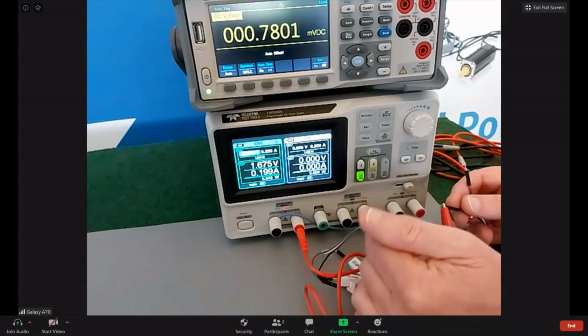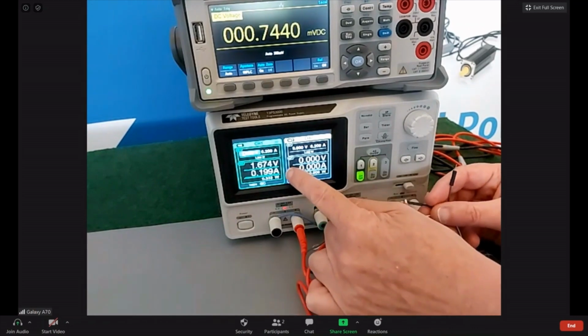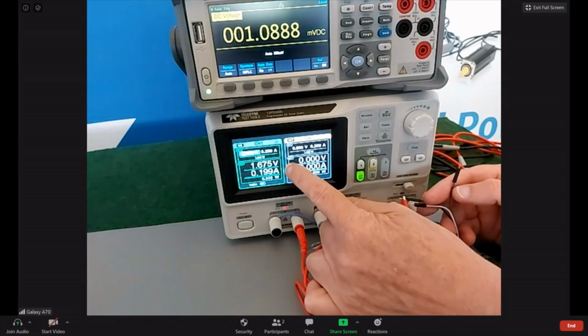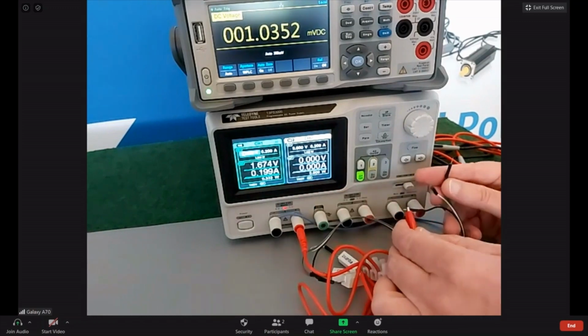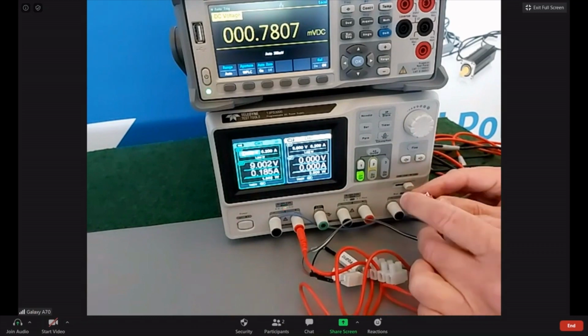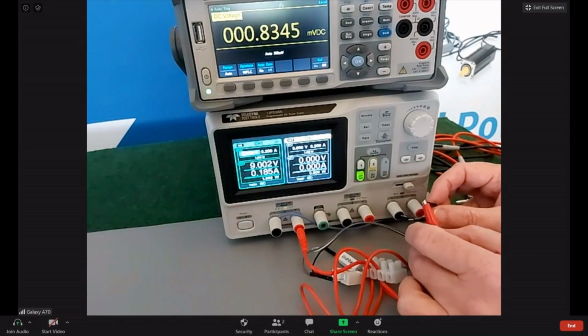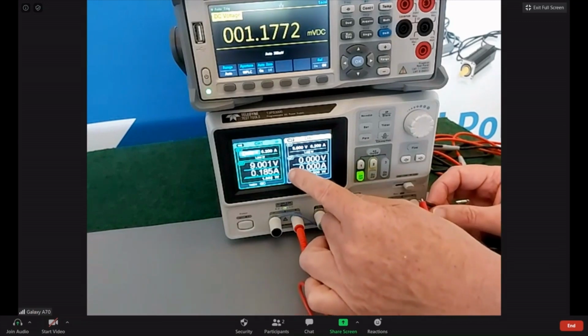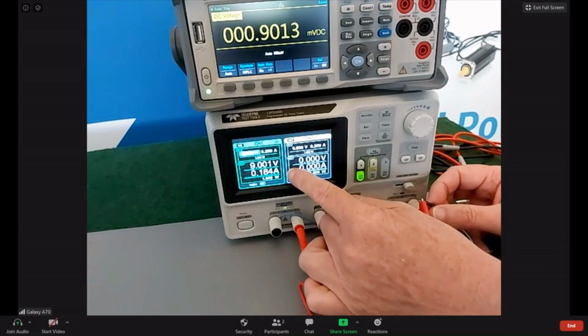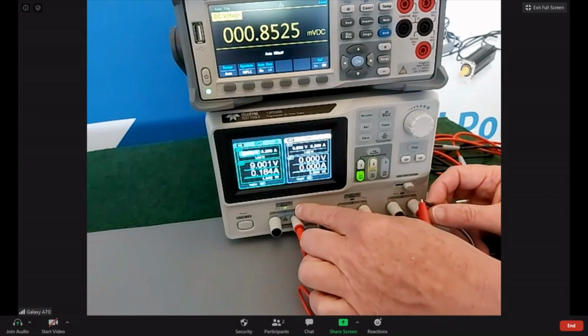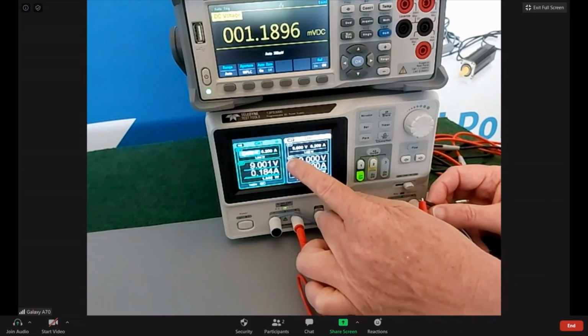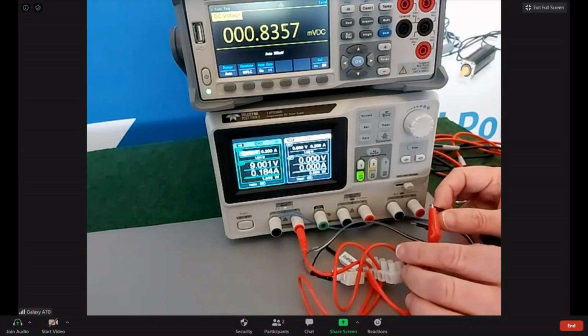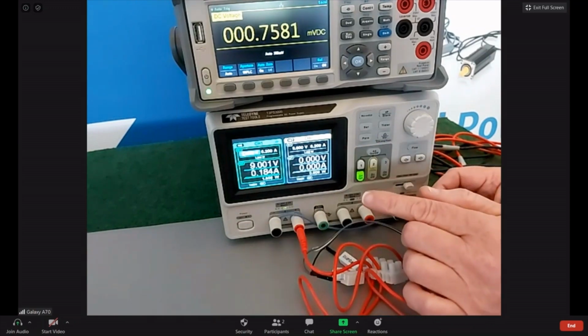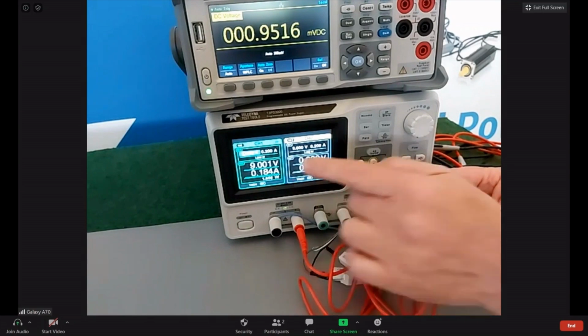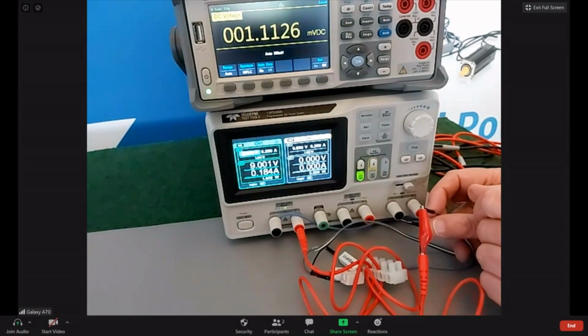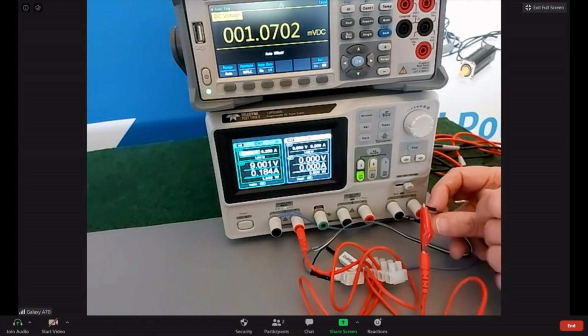Connect up our other load, and we've got the 200 milliamp limit, and it's down to 1.67 volts. Now we connect up our other load, and actually this load is quite low, so it doesn't draw the 200 milliamps. But what's happened is we've switched into voltage mode, and we've been limited by our voltage. So when using constant current, you can use the voltage settings here to stop the voltage getting so high that it damages the DUT.